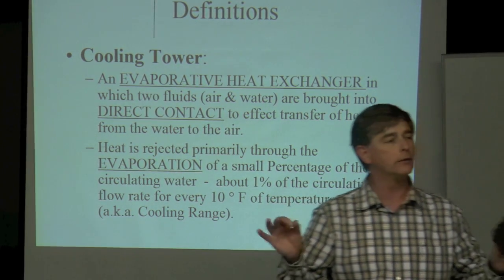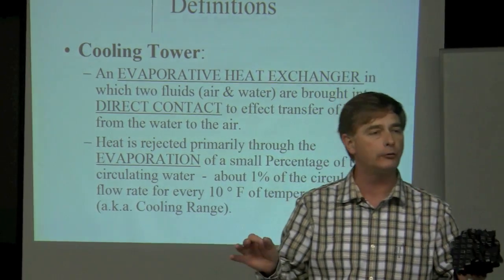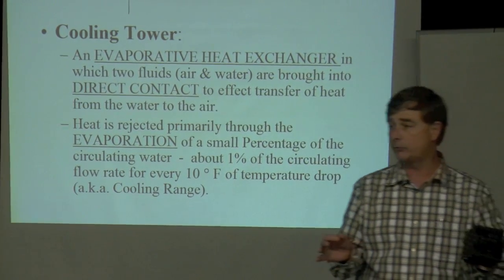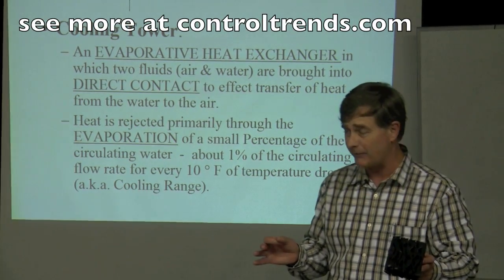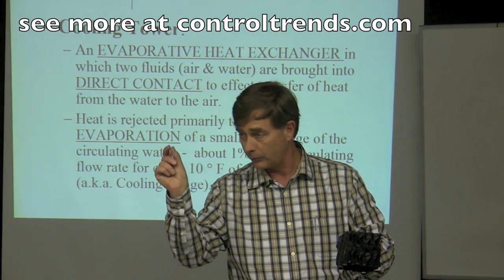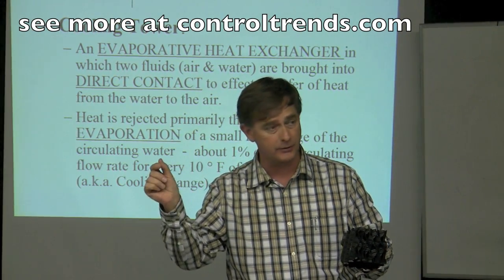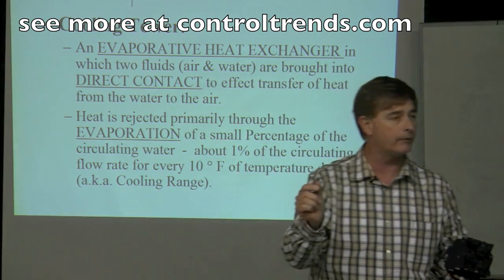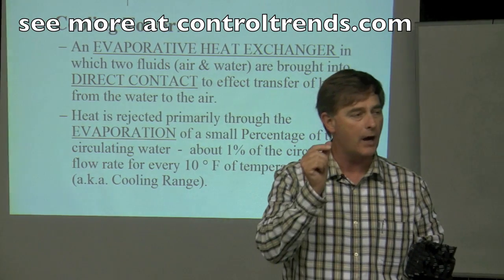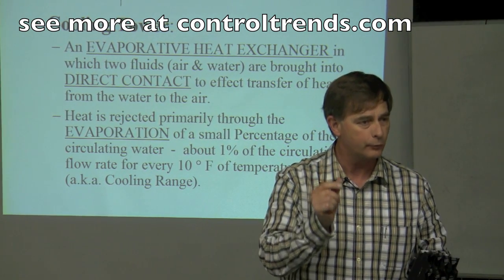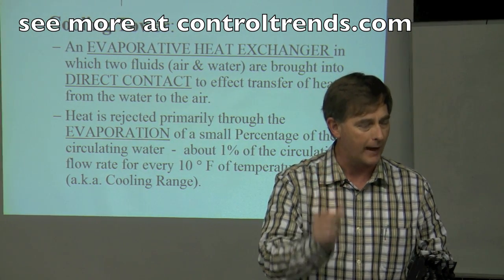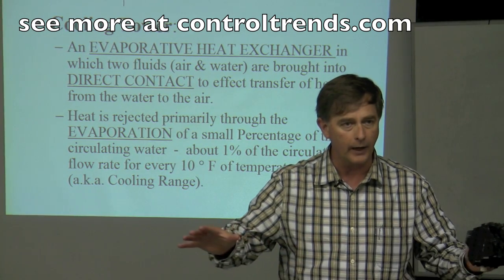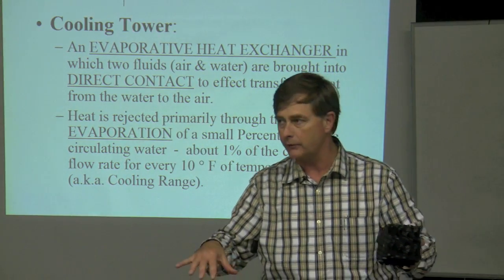What they're trying to do is promote evaporation. Remember the latent heat of vaporization — about 970 BTUs when it changes state. It's the change of state where the work is being done — latent heat of vaporization. A cooling tower does its work through evaporation. You evaporate better if you spread that water out and let the airflow get to it.